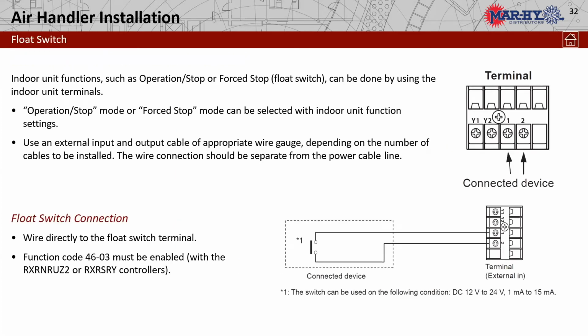They show it again, terminal strip, low voltage terminal strip, 1 and 2. That is where we will make our safety switch connections, depending on what it is. Remember, it's a dry contact. All we have to do is close a switch, and we can program that to be a normally opened or a normally closed, whatever the application may be. Could even use it commercially with smoke fire, things such as that, where we disable the unit, turn it off completely.